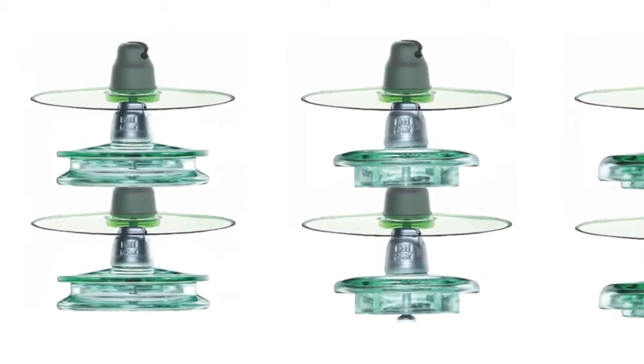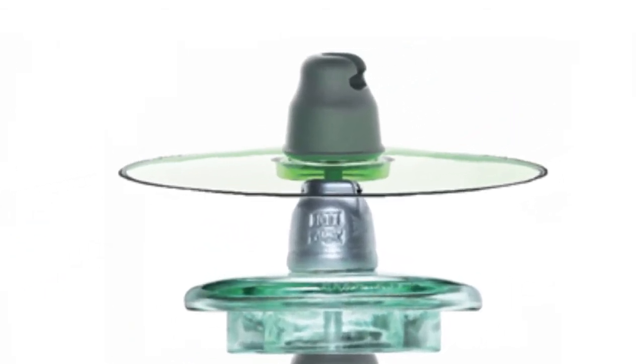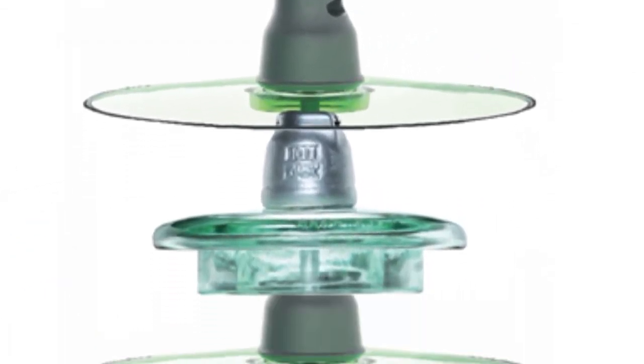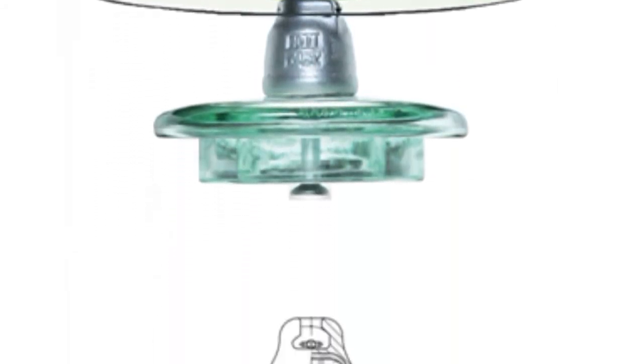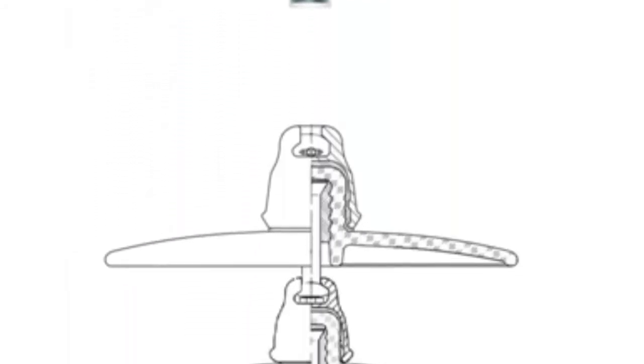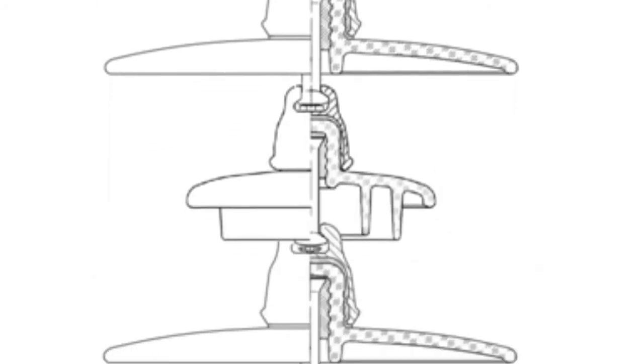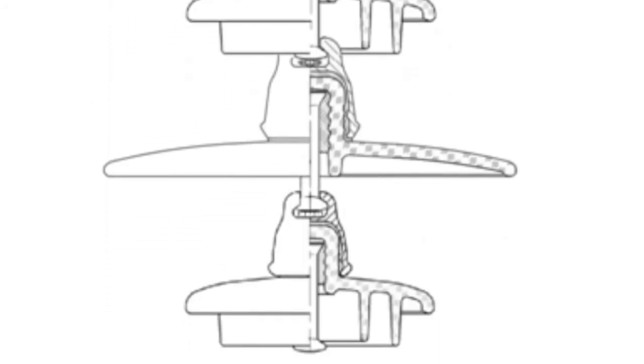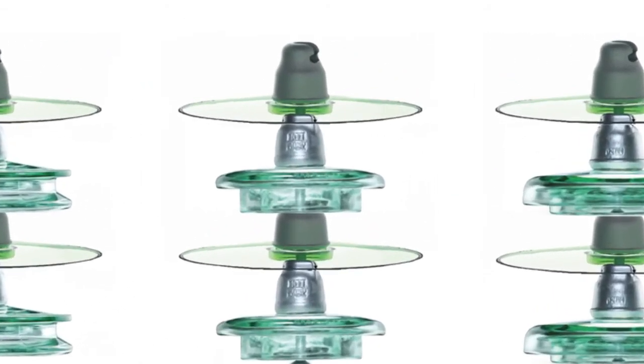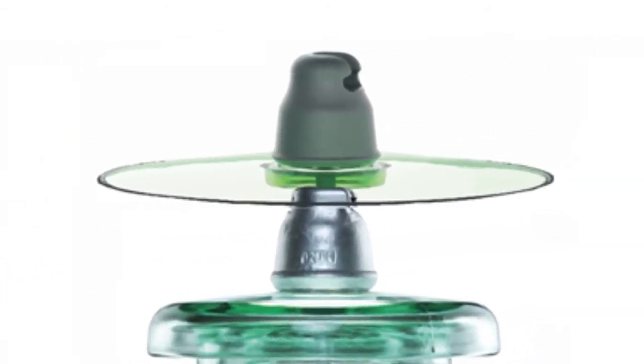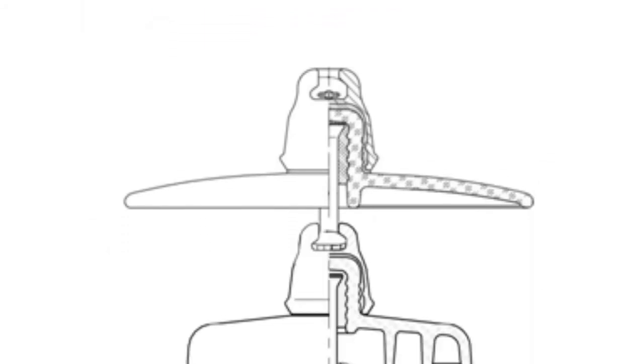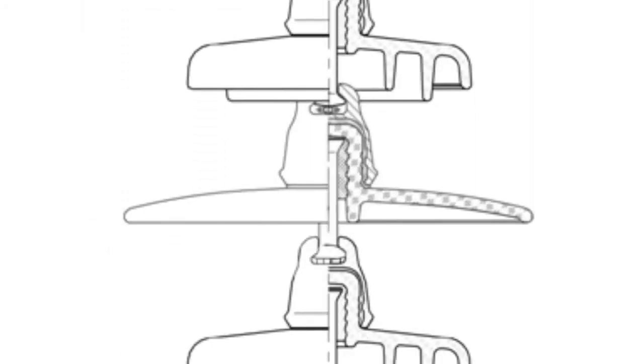Number 3. To achieve the high discharge characteristics of a string, Global Insulator Group offers the use of mixed type strings combining aerodynamic and fog profile qualities. Mixing insulators of different profiles allows increasing the ability to withstand composite pollutions and discharge characteristics by means of interchange of insulators profile, horizontal and vertical ribs. For variation of aerodynamic and fog characteristics, the interchange of insulators of aerodynamic profile and insulators with such characteristics as extreme ribs, insulator with the extended ribs, fog type are used.